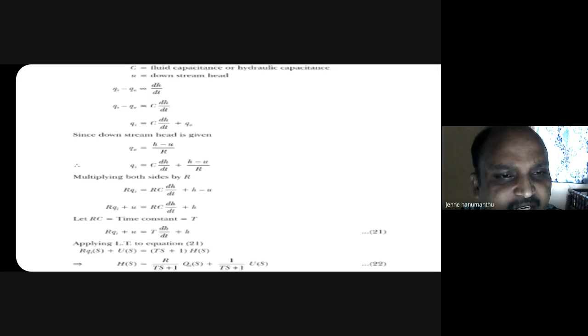The output flow rate depends on the tank head and the downstream head. The outlet water stream flow rate depends on tank head and downstream head. So I am writing like this: Q naught equals (H minus U) by capital R. What is H? Small h is the tank head. What is U? The downstream head, the water outlet from the tank, so that is called downstream head U. And what is R? The resistance provided by the control valve in the tank. So Q naught is written like this.